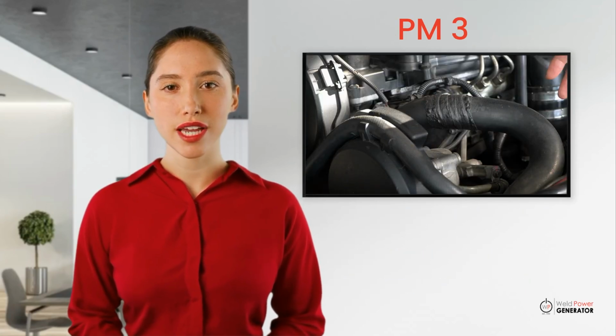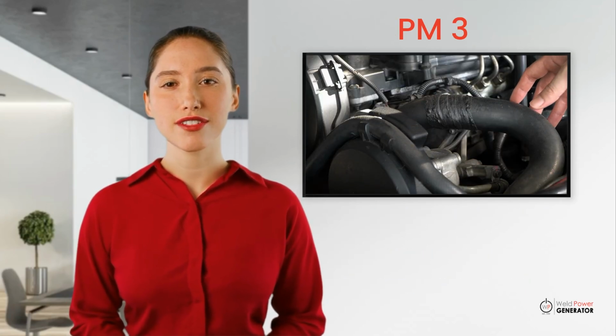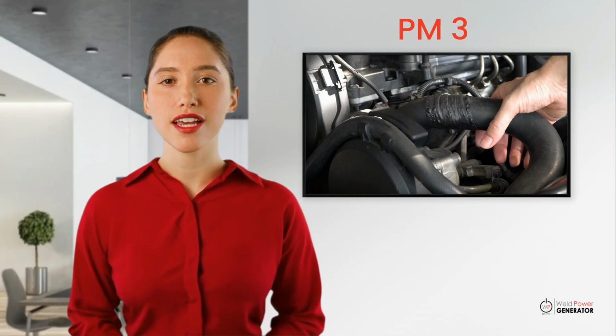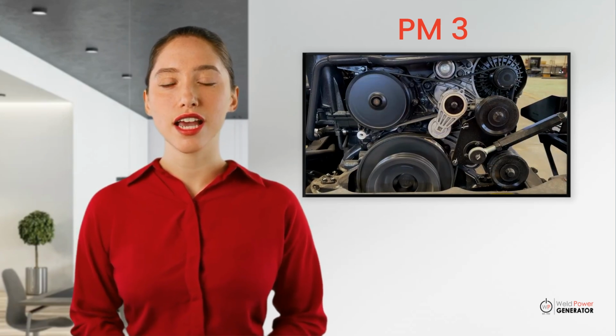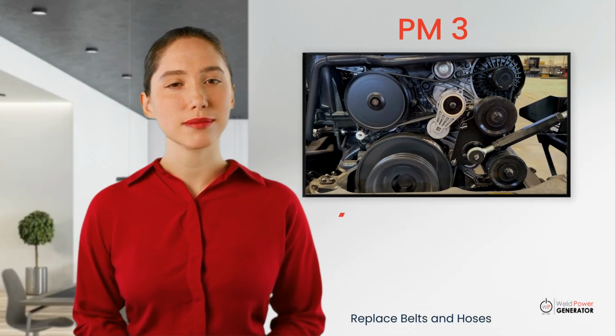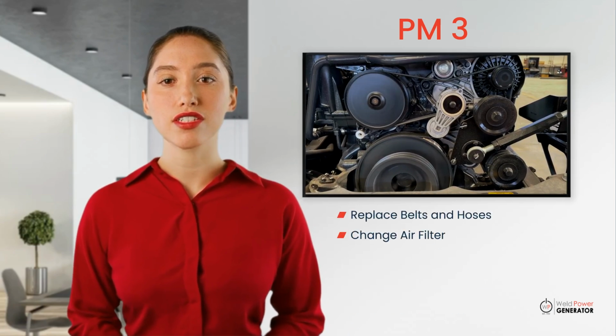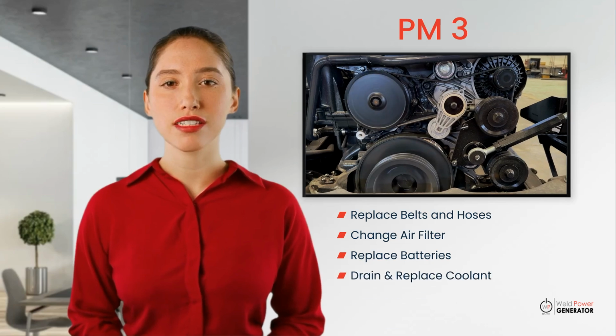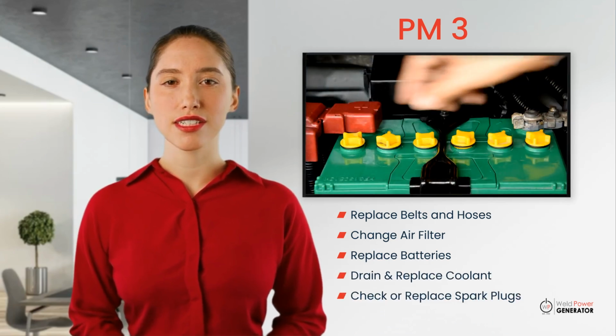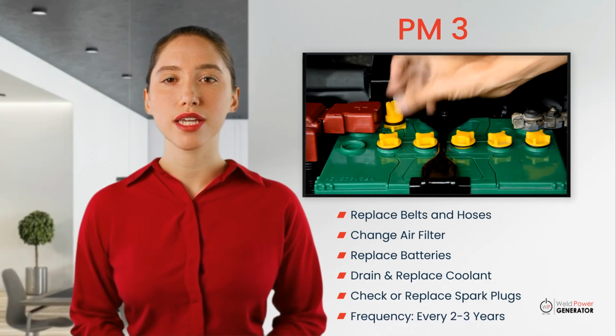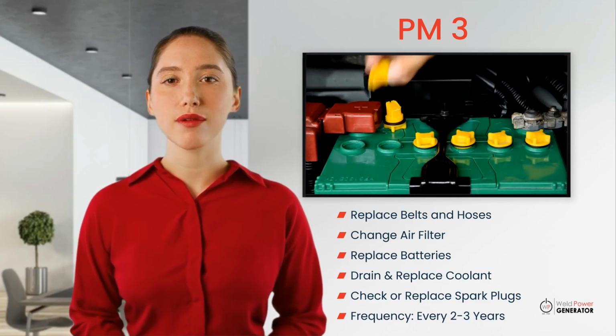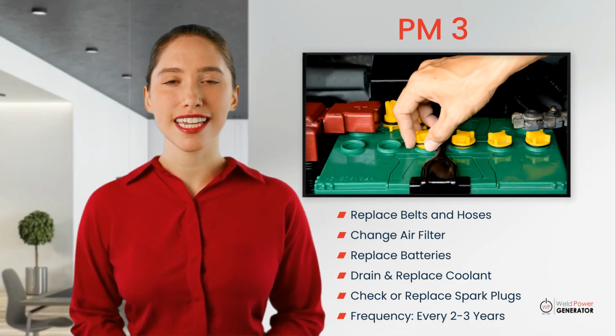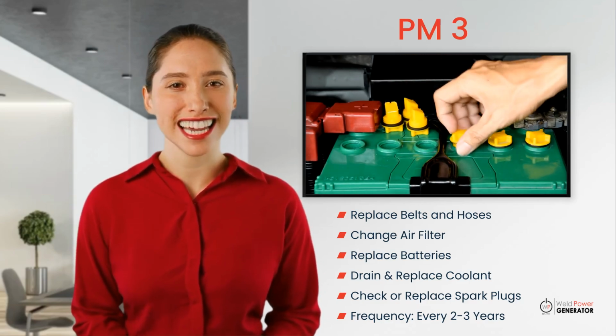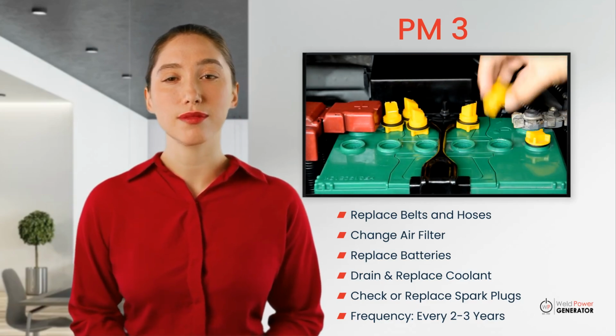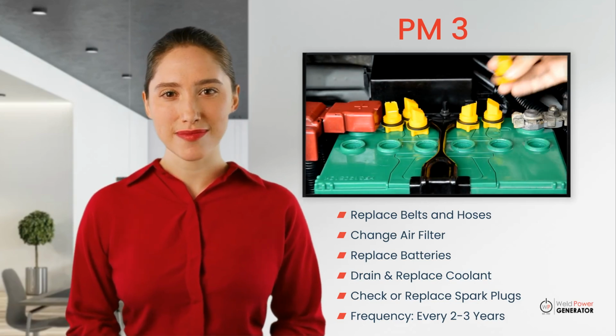Preventative Maintenance Level 3, or PM3, is a detailed service that addresses wear and tear that might not be visible in routine checks. In a PM3, we replace belts, hoses, and air filters, change batteries, drain and replace coolant, and check spark plugs. This level of service is typically performed every 2 to 3 years or based on hours of operation. PM3 is critical for generators operating in demanding conditions and ensures long-term reliability.